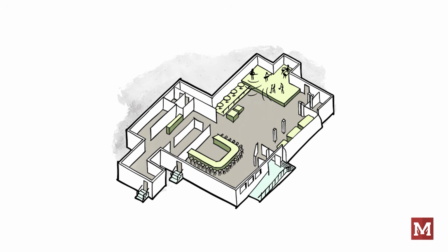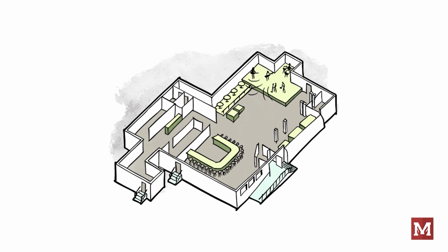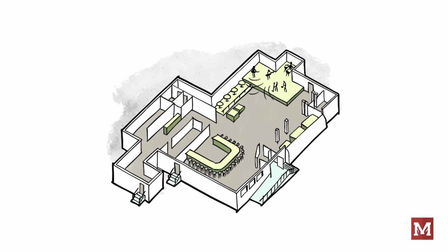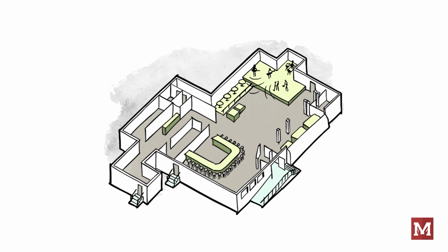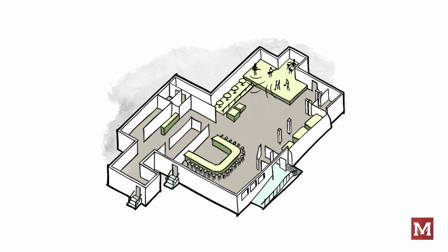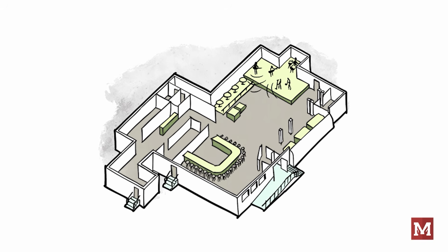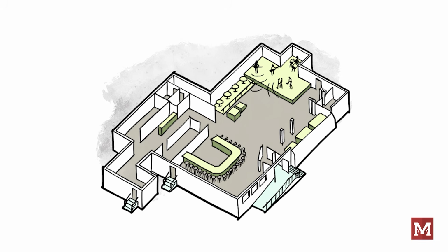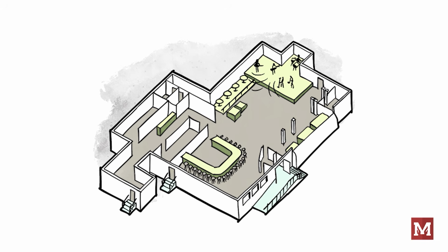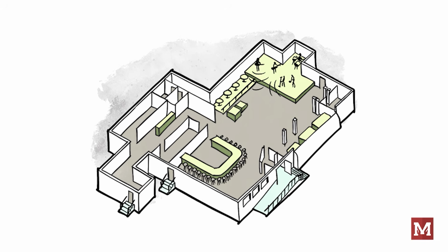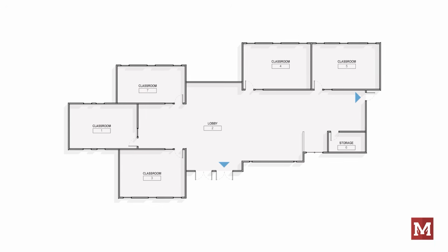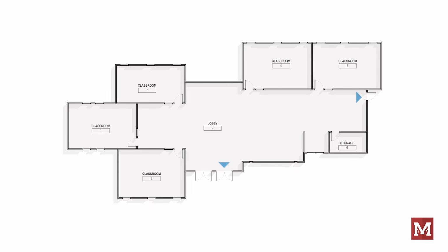Meaning if I size my exits equally, that's 50% exactly, and I meet this requirement. If I have disproportionately sized exits, this means that the bigger exit doesn't actually help for egress purposes. It's still an exit, but that extra width doesn't do anything for exit capacity. The more restrictive, the smaller exit would govern. More specifically, computationally, 2 times the width of the smaller exit would be the allowable exit capacity.